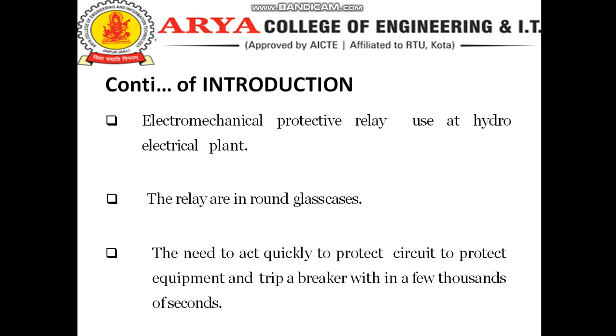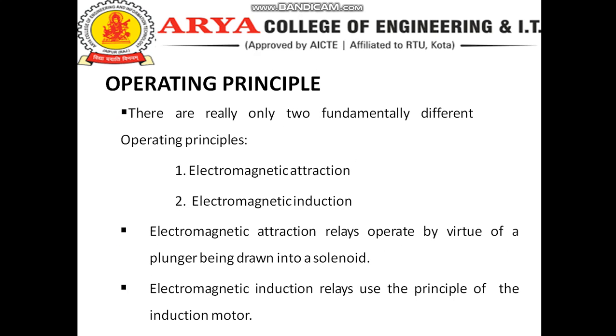seconds. Operating principle. There are really only two fundamentally different operating principles: the electromagnetic attraction principle, and the second one is the electromagnetic induction principle. The electromagnetic attraction relay operates by virtue of a plunger being drawn into a solenoid, and electromagnetic induction relays use the principle of the induction motor.